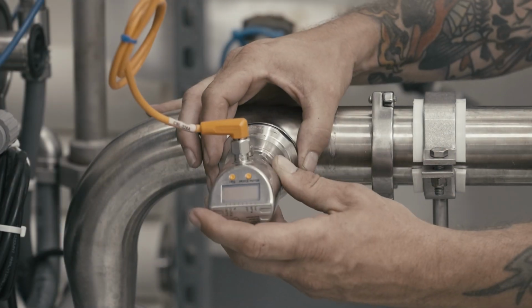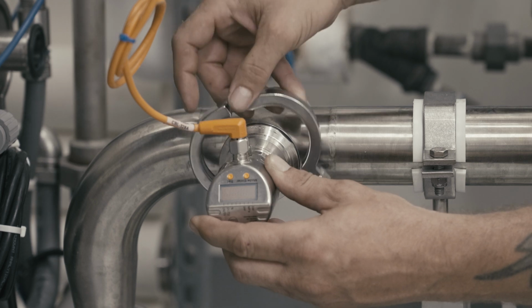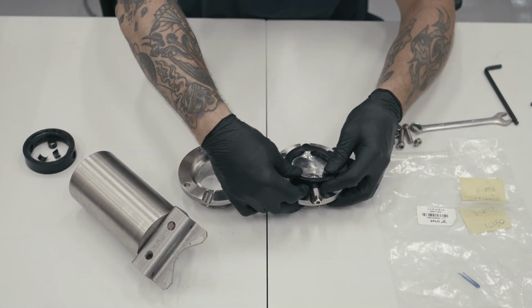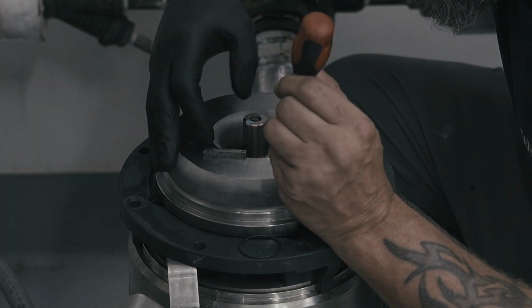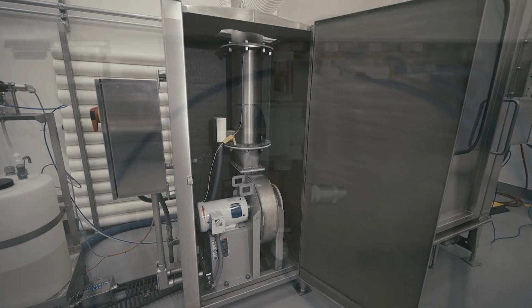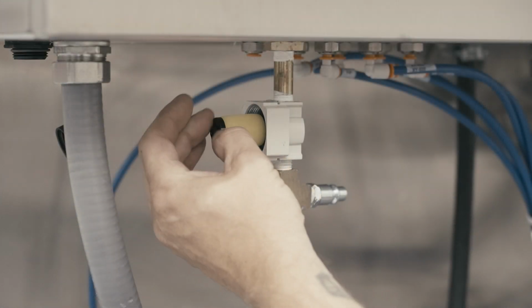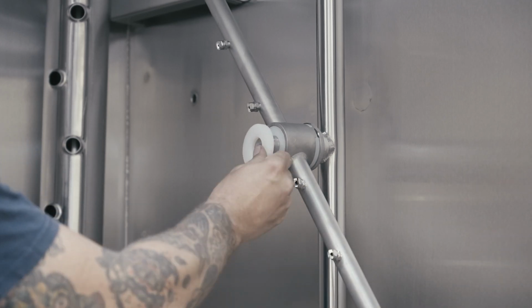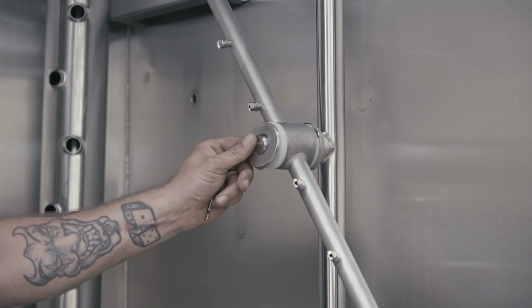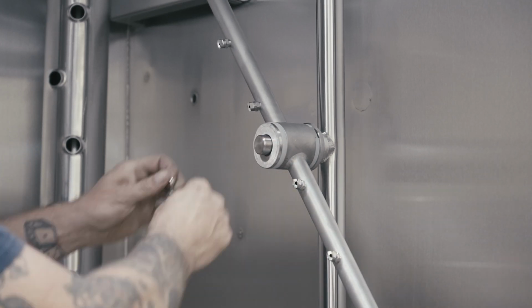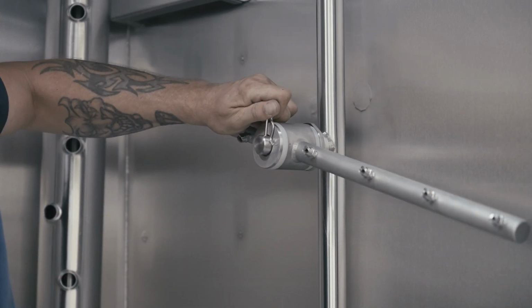Typical preventive maintenance activities include replacement of tri-clamp gaskets, inspection and replacement of valve and check valve gaskets, inspection and replacement of major pump gaskets and O-rings, chemical pump and hose inspection with replacement as required, and inspection and replacement of instrument air filters. For COP equipment like parts washers, inspection and replacement of chamber door gaskets and seals, as well as inspection for proper spray nozzle operation, is included.